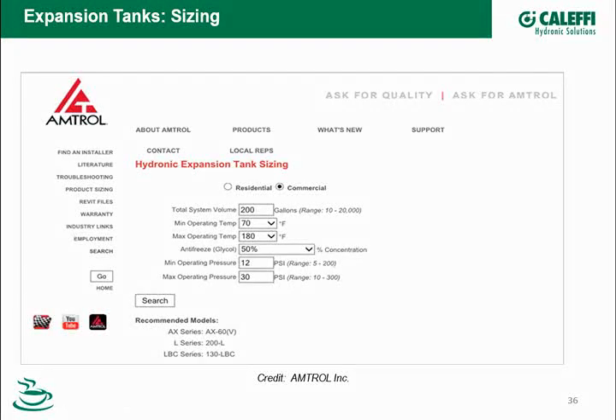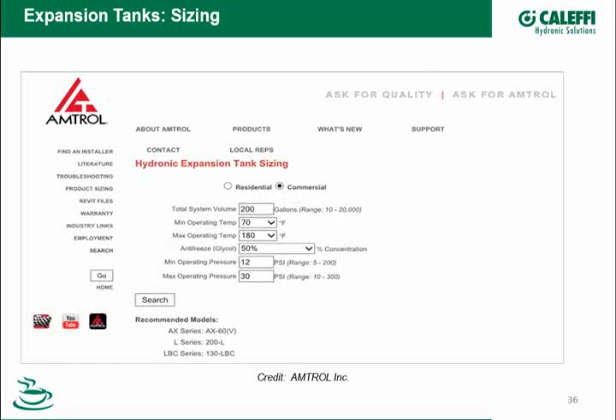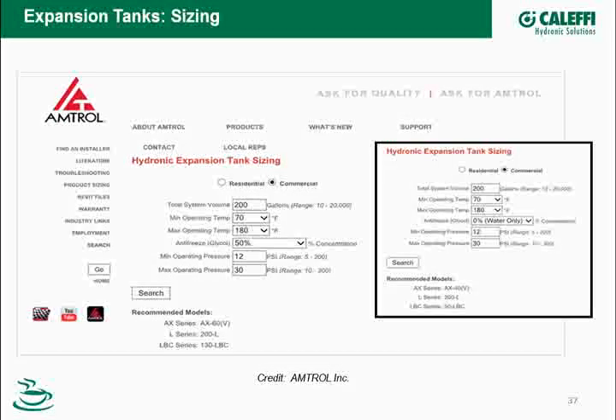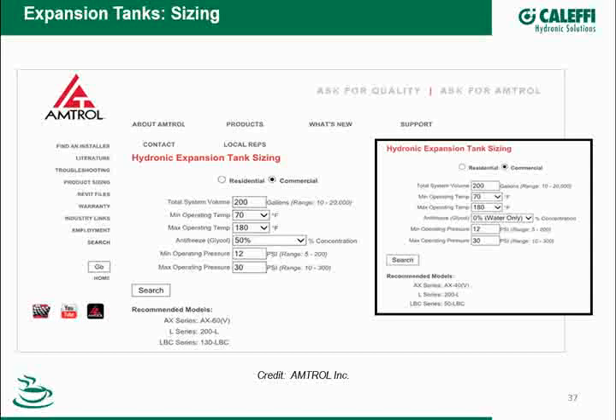So if I'm looking at this system here, 200 gallons total volume, 70 to 180, 50% glycol, minimum pressure 12, maximum pressure 30. These recommended tank models at the bottom are based on the expansion of glycol. If I compare that to water alone, I'm doing an AX40. With glycol, I'm jumping up to an AX60. So doing an LBC series, I start out at a 50 with water, and I'm up to a 130 with glycol. The reason the L series didn't change from a 200L is that's the smallest L series tank they offer. So that's why that one didn't change. But from the aspect of system design, glycol has to be accounted for because of the much higher expansion rate than water.